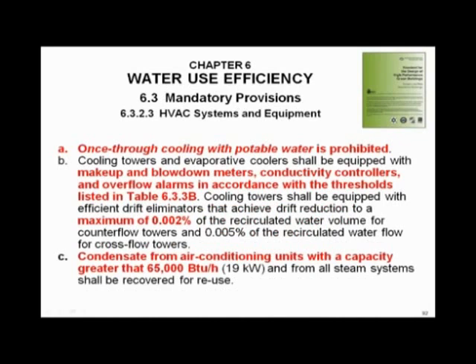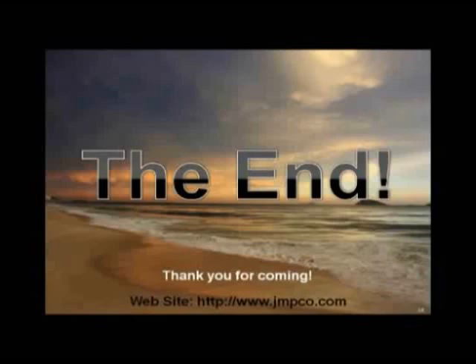ASHRAE 189.1 also requires conductivity controls to manage blowdown — that's going to be a given. Look at item C: any condensate from air conditioning units over 65,000 BTUs — that's five and a half tons — you've got to collect it and reuse it. This is the green building code already adopted by the Army Corps of Engineers, and many cities have adopted it as well. It's not yet in 90.1, but it's coming. If you're building to the green building code, you'll need to collect that condensate and reuse it.